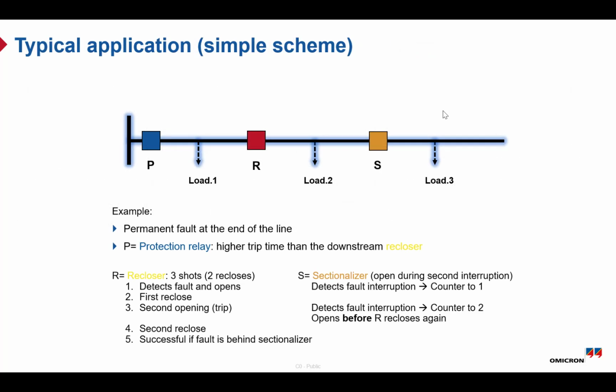So let us take a look at a typical application example using a simple scheme. Here, P represents the incomer, R represents the recloser, and S represents the sectionalizer. In this case, we have a radial distribution feeder coming from a substation. Along the line, we firstly have a feeder relay at the substation, then a recloser installed further down the line, followed by a sectionalizer with different groups of loads, load 1, 2, and 3.